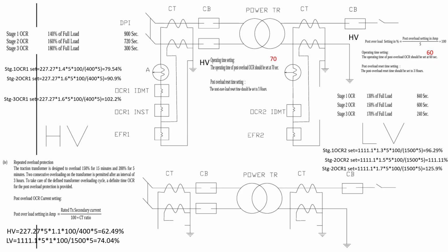Then post overload. What is post overload? After tripping on overload, for how long before you can close it again, because continuous overload is not good for the power transformer. So you cannot operate it again until the time setting has elapsed. In summer it is 70 seconds on the HV side, and on the LV side it is 60 seconds.